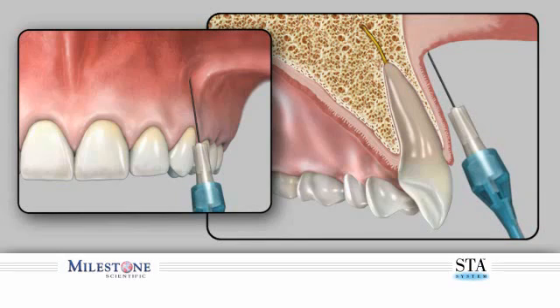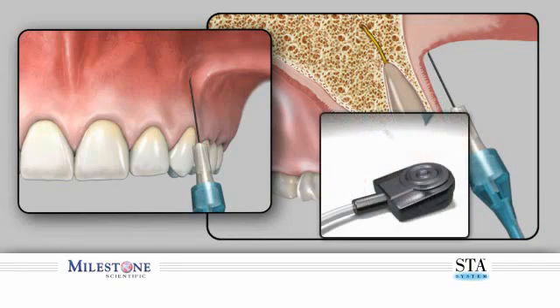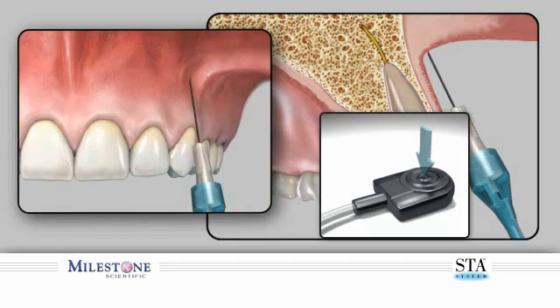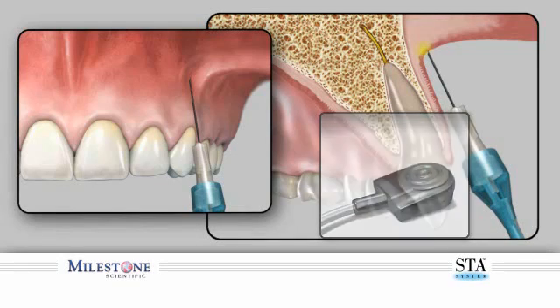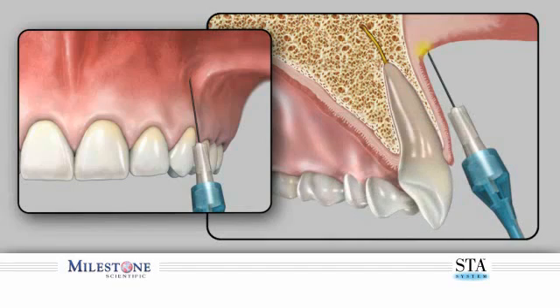Just prior to needle insertion, initiate cruise control by depressing the foot control lightly. After three beeps, the STA system will announce cruise. Upon hearing the cruise announcement, remove your foot from the foot control pedal if you desire to use the cruise feature. This begins the anesthetic flow to the injection site.